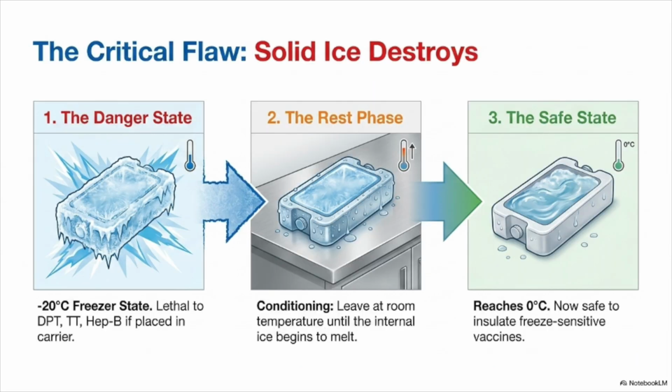However, there is a critical flaw to be aware of. Solid ice destroys freeze sensitive vaccines. In the danger state, the ice pack is at minus 20 degrees Celsius, straight from the freezer, and this is lethal to DPT, TT, and hepatitis B if placed directly in the carrier.